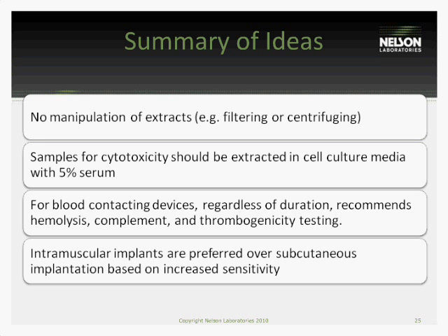So what's happening there is your neat solution, or your 100% pure extract, is getting mixed into an MEM and is getting diluted, compared to when we extract straight into the culture media with 5% calf serum. So when you're doing a cytotoxicity test, make sure your lab is performing the test with a 5% calf serum. It can have an impact on results, and the FDA prefers the 5%.